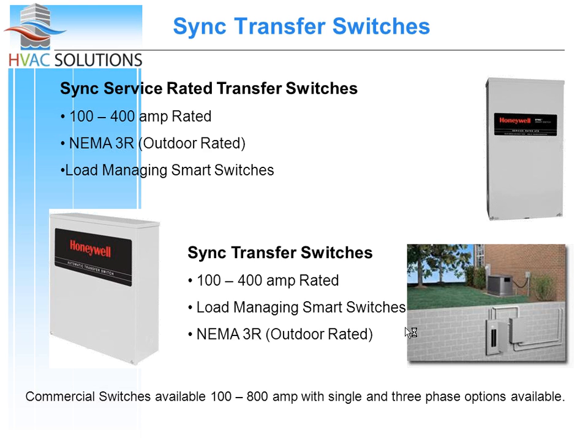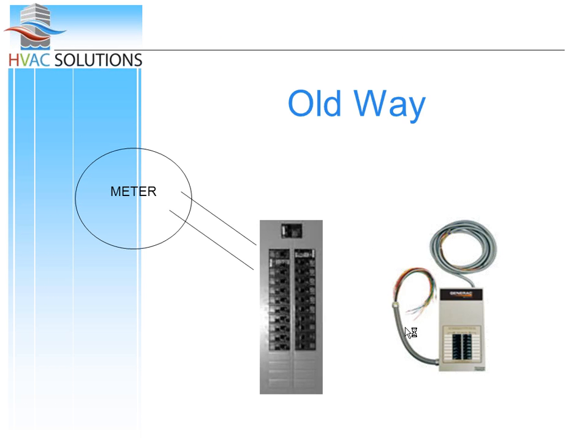Sometimes I get asked, what does service rated mean? Basically, service rated means you can mount this transfer switch before the customer's circuit breaker box because it has its own designated circuit breaker inside of the transfer switch. A non-service rated transfer switch would not have that circuit breaker, and it would go after the customer circuit breaker panel.